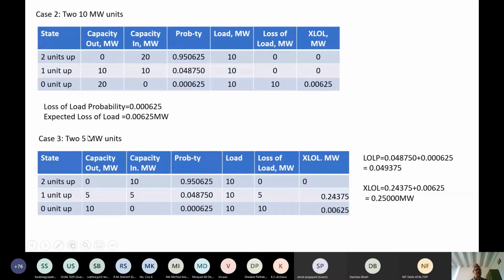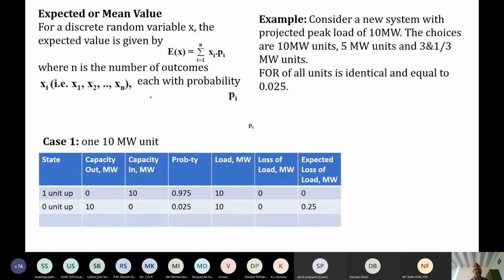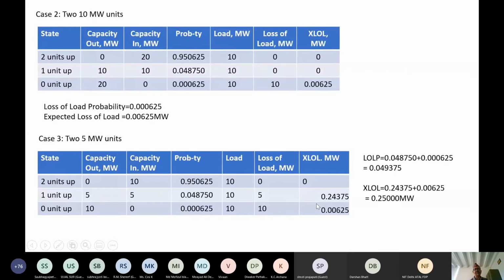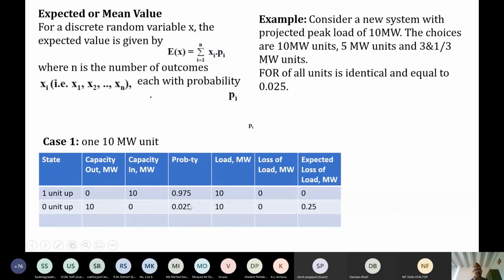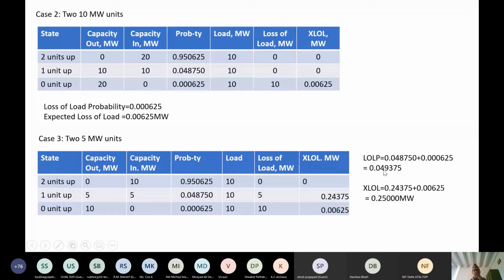So in this case, 2 5 megawatt units. Again, you have both the units available, load loss is 0, only 1 unit available, load loss is this much, both the units unavailable, load loss is this much. You can see that in the case of 2 5 megawatt units, the expected loss of load is the same as that of the 1 10 megawatt unit case. This was expected load loss of 0.25, here also it's 0.25, but loss of load probability there was 0.025. Here loss of load probability is 0.049375. The loss of load probability has increased here.